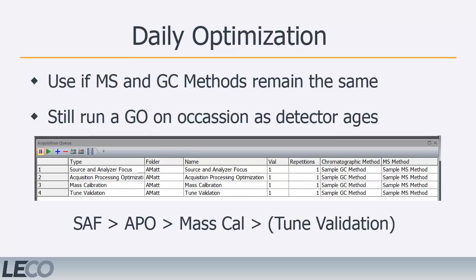If the user is continuing to use the same unchanged mass spec and GC methods for sample analysis, then a daily optimization schedule can be used. The detector voltage should not change daily, but needs to be rerun from time to time as the detector ages. The daily optimization sequence includes an SAF, an APO, and a mass cal.